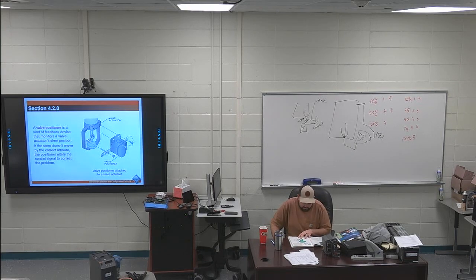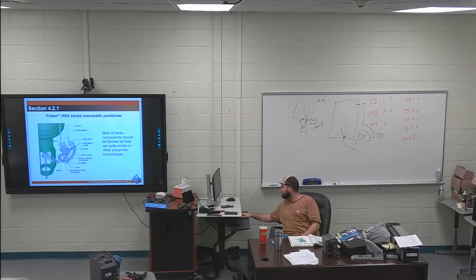Page 26 and 27. We're still going into more of how pneumatic and electro-pneumatic positioners work. Yeah, you can see how they attach to the front. Inside, I'm not taking the front cover of this off, but if I take the front cover off, you have this stuff on the inside, and this is how you adjust and calibrate the valve positioner. Page 27, the first sentence on page 27 is highlighted.